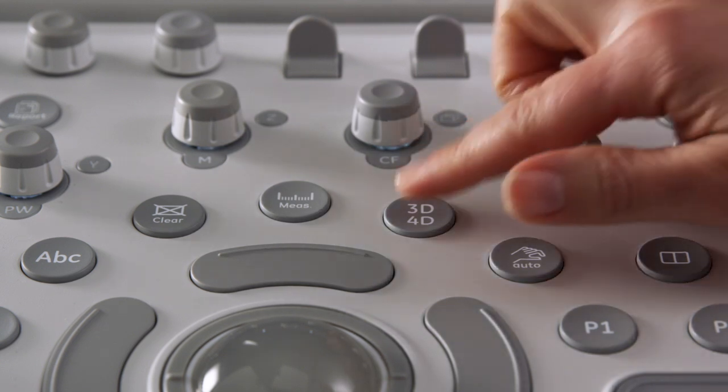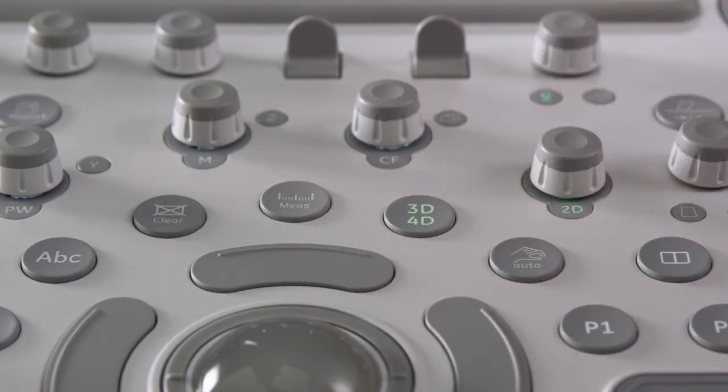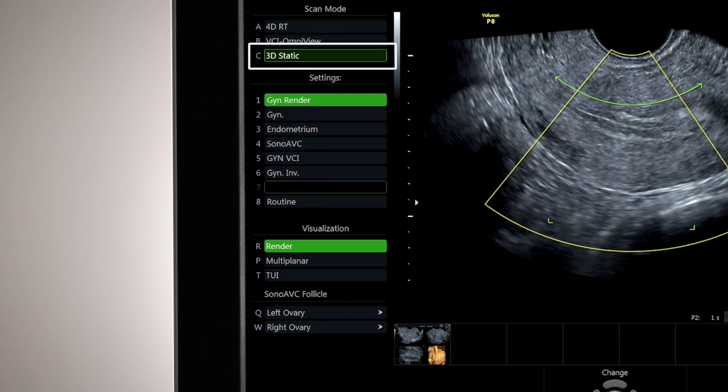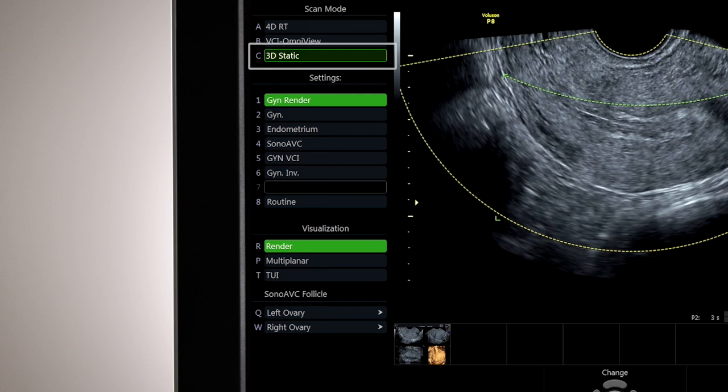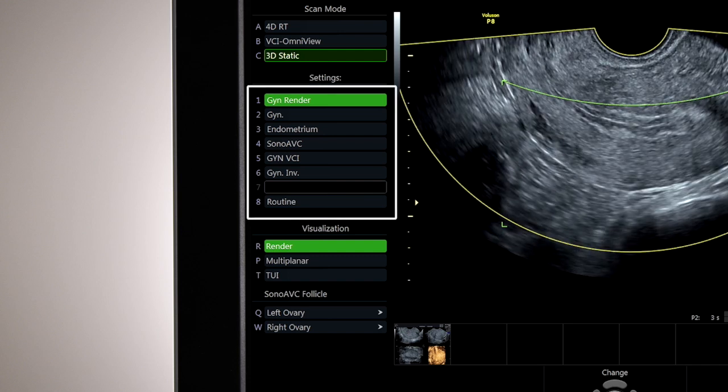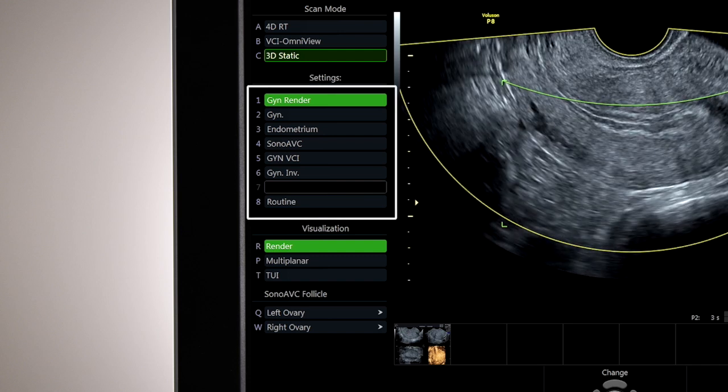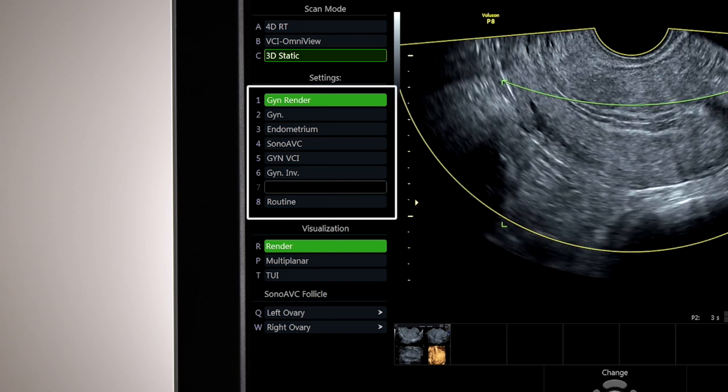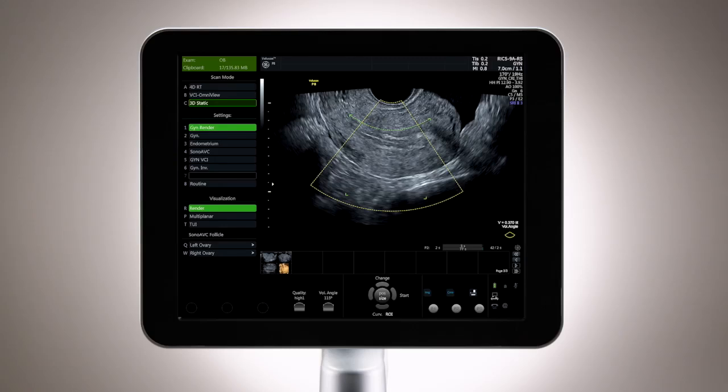To start the acquisition, select the 3D, 4D hard key and choose 3D from the display menu. 3D has its own set of presets, so when preparing to acquire a volume, select an appropriate 3D preset. A yellow region of interest, or ROI box, will appear on the monitor that you will place over the area that you want to acquire as a volume.